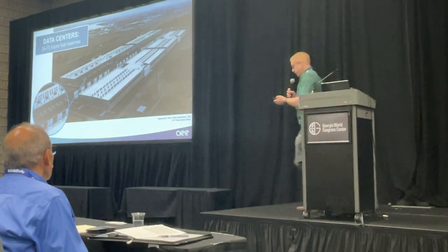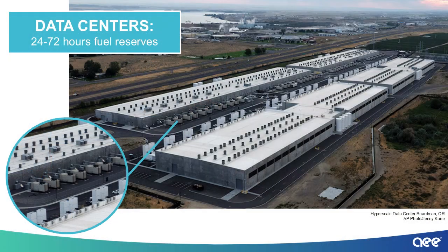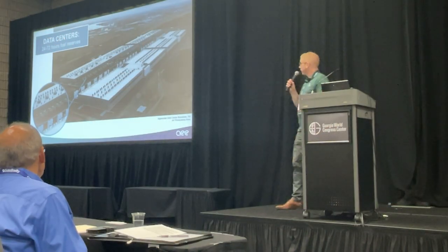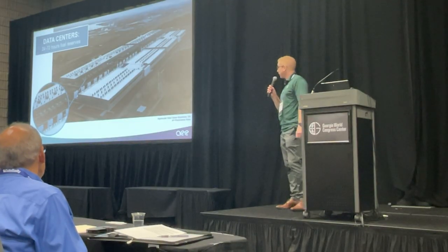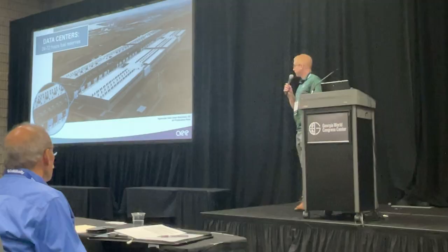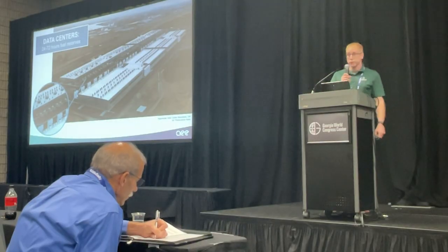This is a hyperscale data center in Boardman, Oregon. Along this row of buildings, each individual box is a 2.5 megawatt genset, and along this other row, slightly different configuration and package, but also 2.5 megawatt gensets. There are 4 more sites in this same area with similar layout, so 250 megawatts of backup or emergency power for 24 to 72 hours, a significant amount of energy requirement there.